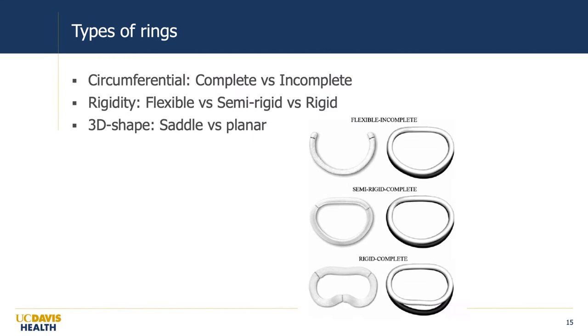There have been many types of surgical rings developed over the last several decades by different companies and surgeons, many named after the surgeons who developed them. We think of rings in a few categories: complete or incomplete — either circumferential or open; their rigidity — flexible band, semi-rigid, or rigid; and finally whether they're planar or have a more complex saddle shape, or in some cases a very aggressive posterior saddle shape.